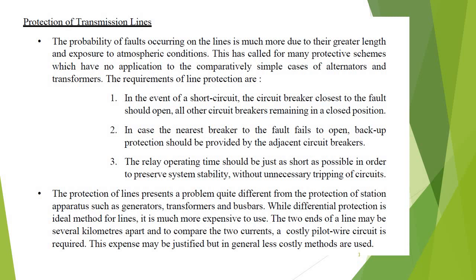What are the requirements of line protection? In the event of a short circuit, the circuit breakers closest to the fault should open, with all other circuit breakers remaining in a closed position. In case the nearest breaker to the fault fails to open, backup protection should be provided by the adjacent circuit breaker.